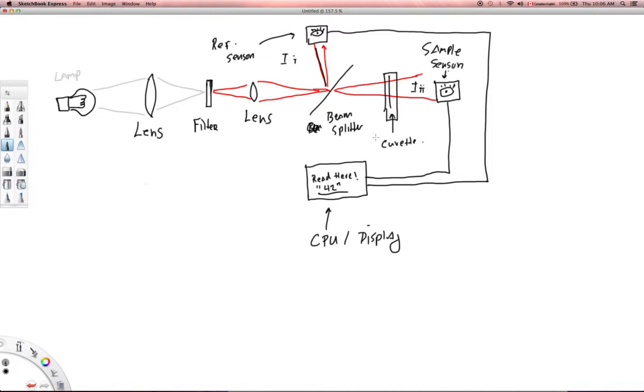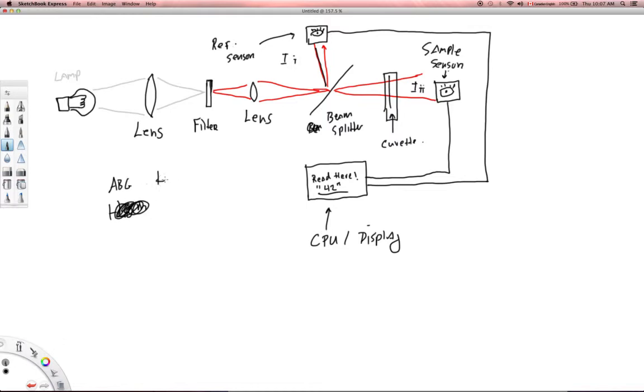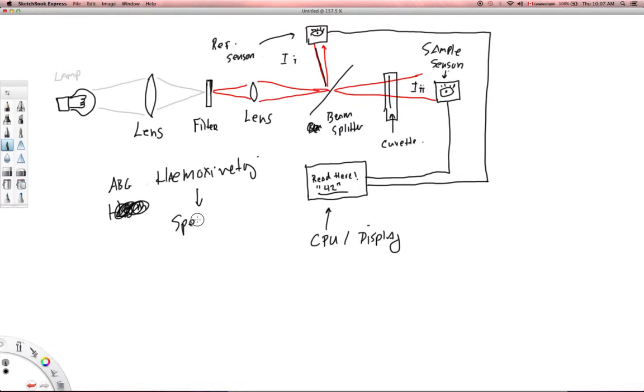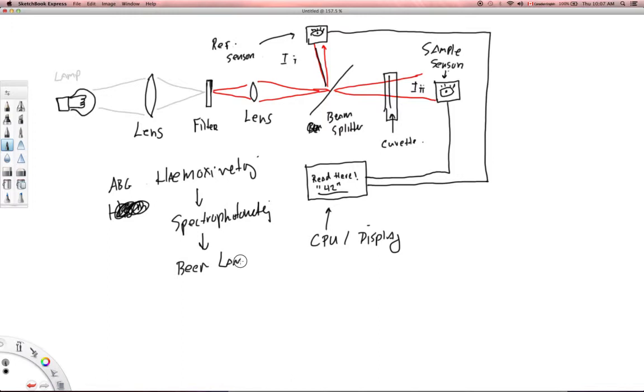All right, so this is how, in a very simplified form, how an ABG machine works. This is how hemoximetry, specifically, hemoximetry, and it uses the principle of spectrophotometry. Spectrophotometry relies on the Beer-Lambert Law to figure out what the concentration is, and ultimately what the partial pressure is.